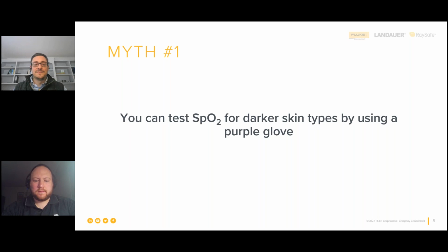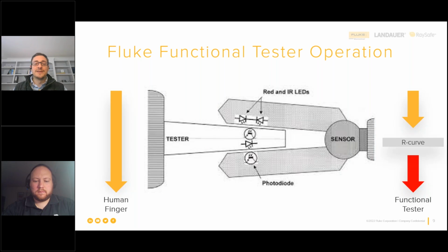slides here. And the first is how a Fluke Biomedical SpO2 functional tester works, right? At the end of the day, they pretend to be a finger. You can see here on the left how light would normally flow straight through a human finger. And these functional testers, although they're not simulating a finger, they fool the SpO2 monitor into thinking that it is monitoring an actual finger. So they take light from the pulse oximeter, they run it against an R curve inside the device, and then they emit the right amount of light to the detector. The tester has two light detectors with a filter over one of them, so it can discern the type of light, right? It's either red or infrared.